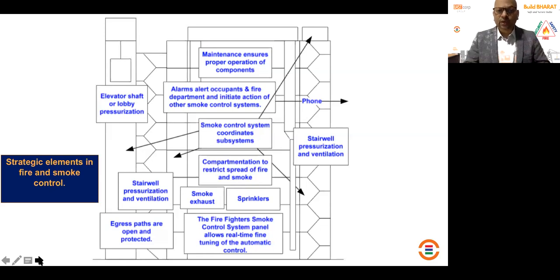When you look at smoke control systems, what systems get coordinated or communicated? First and foremost is the fire alarm system. Your triggering point for the ventilation system, smoke extraction system, or smoke control system must come from your fire alarm detection system. It cannot be manual, because then you're going to lose a lot of time. If it comes from a reliable fire alarm source, it will be more effective. So first and foremost is the smoke alarm system that communicates.